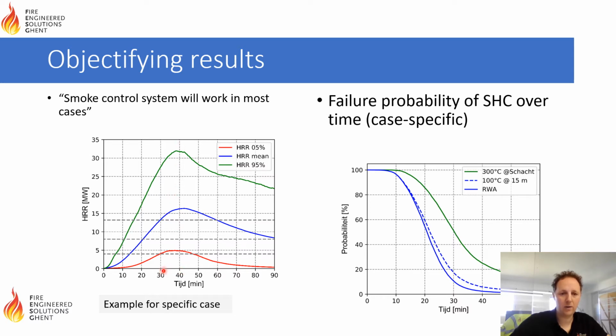So assuming the fire brigade arrive at 30 minutes, we know that there's a 5% chance that the fire is not higher than 4 megawatt. There's a 50% chance the fire is not higher than 13 megawatt, and there's a 95% chance that the fire is not higher than 27 megawatt. So this objectifies the results in a way that, depending on the time of arrival of the fire brigade, you can say what's the probability of failure of the smoke and heat control system. For instance, looking at the temperature at the shaft. If the fire brigade arrives after 30 minutes, there's a probability of failure of 50%, while if the fire brigade arrives after 15 minutes, there's only a probability of failure of, let's say, less than 5%. So pretty interesting to link both.